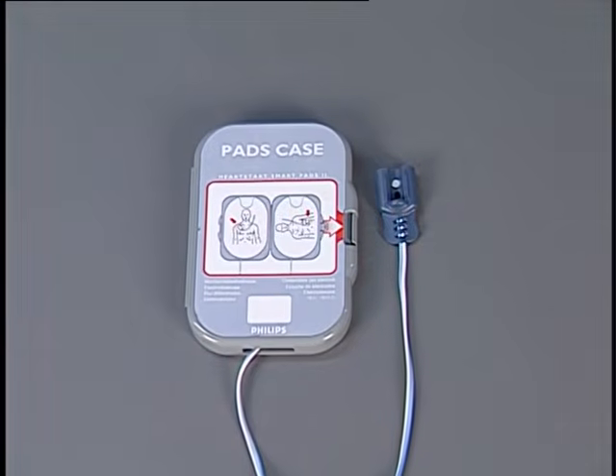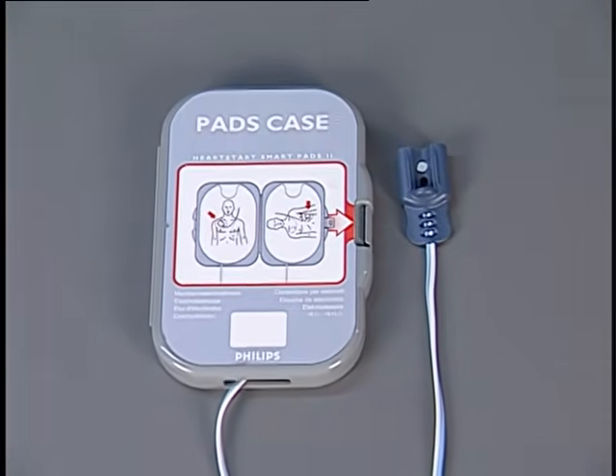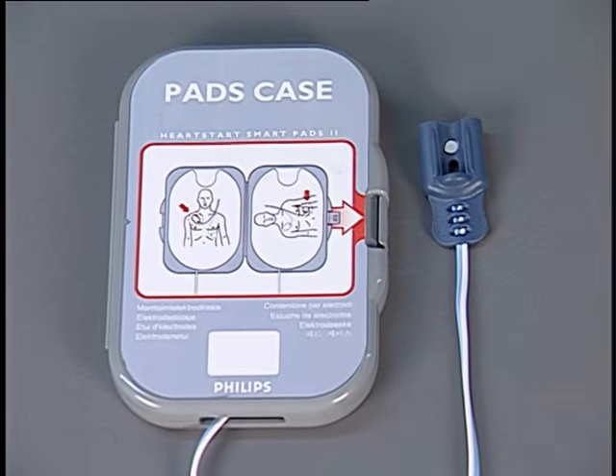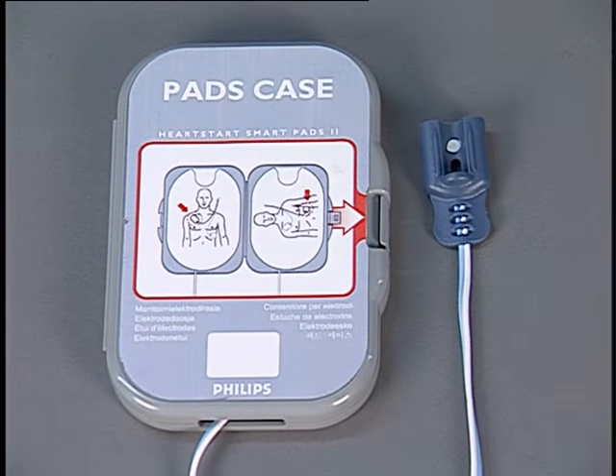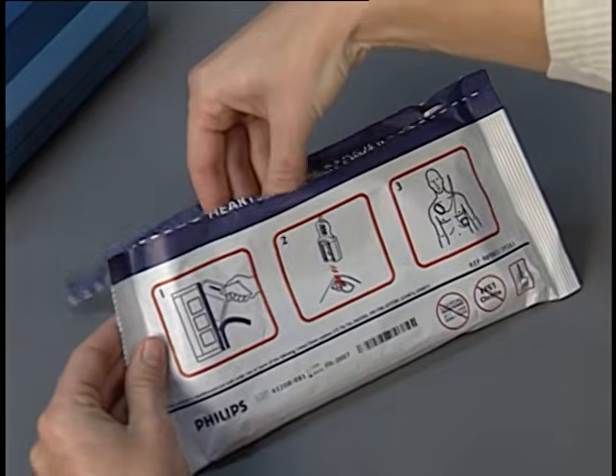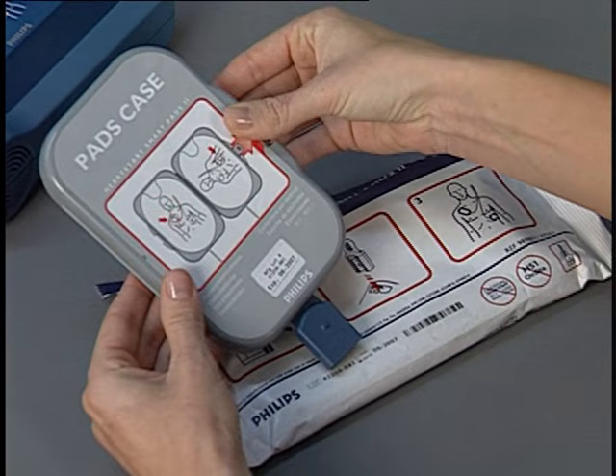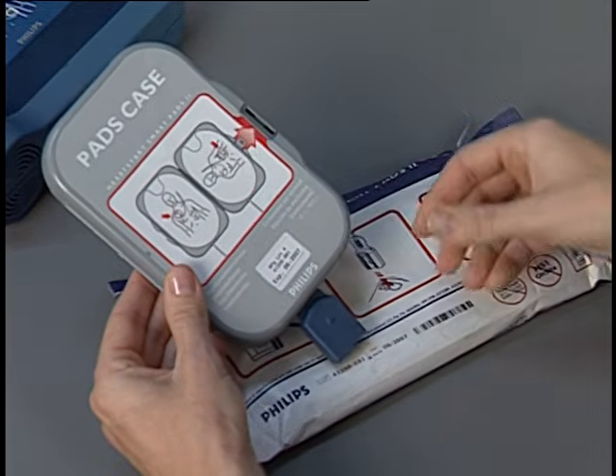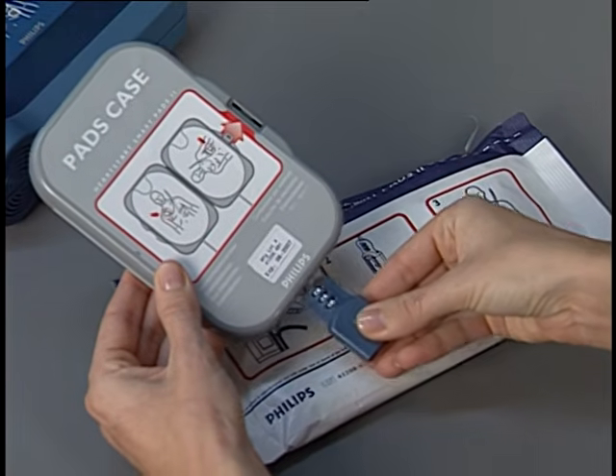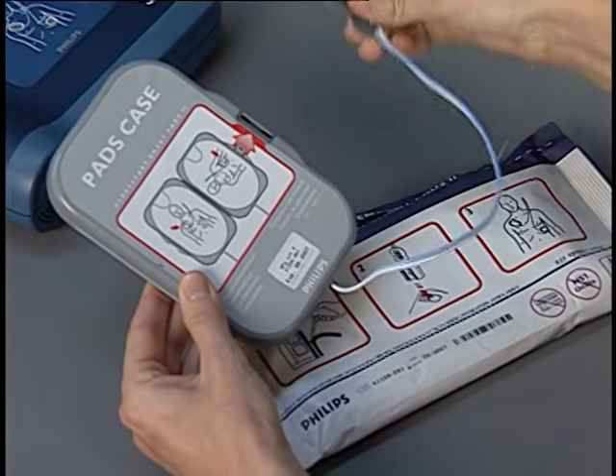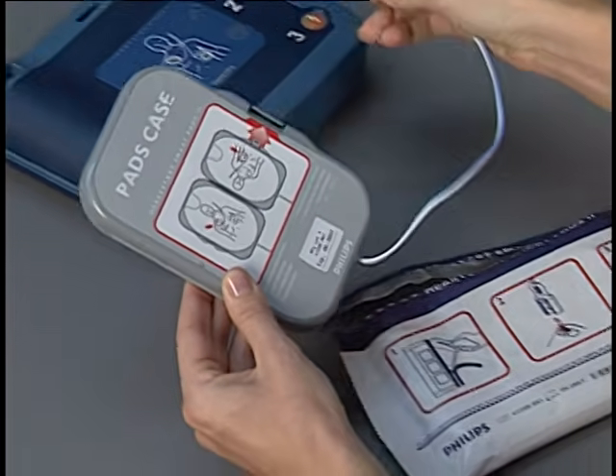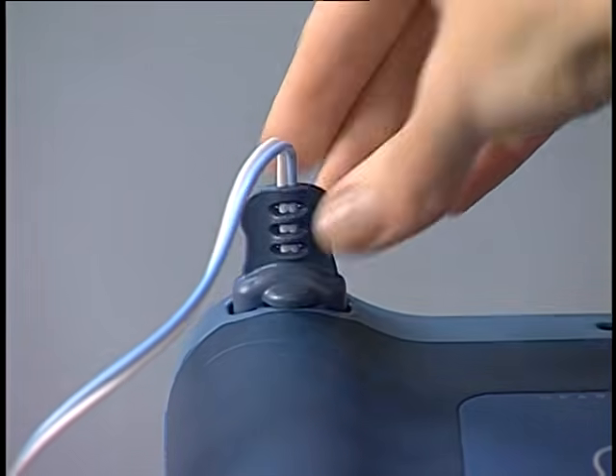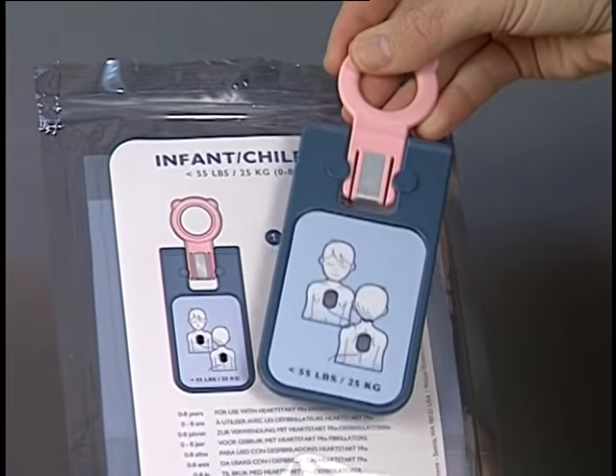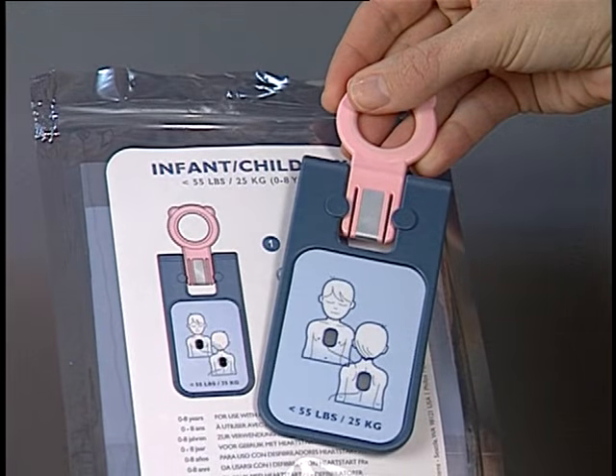The FRx uses specially designed HeartStart Smart Pads 2, which allow the defibrillator to be stored with the pads set pre-connected. Open the pads package and remove the pads case. Do not open the case until the pads are needed for use in an emergency. Each gray pads case contains 2 adhesive pads. The pads cable extends from the case and ends in a connector plug. Plug the connector plug into the defibrillator, snapping it firmly into place. With the optional infant-child key, the same pads used to treat adults are used to treat infants and children.